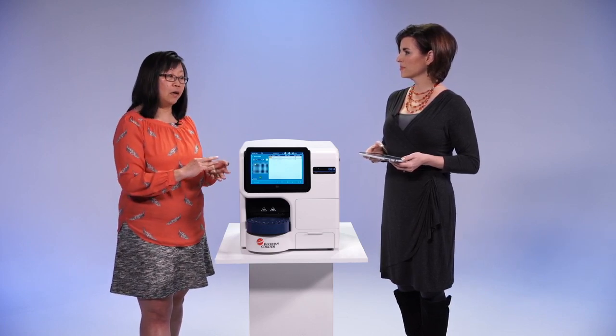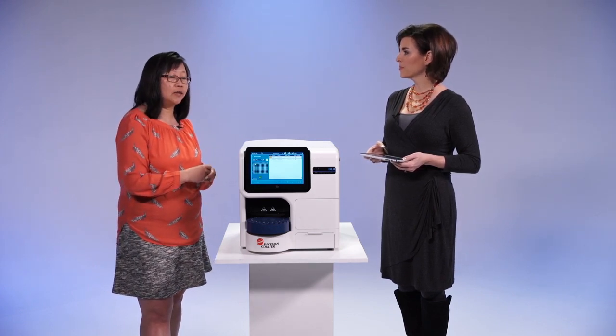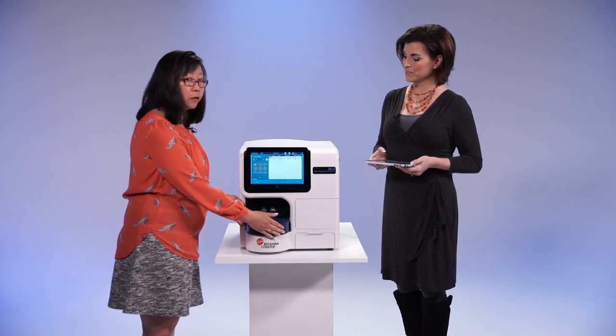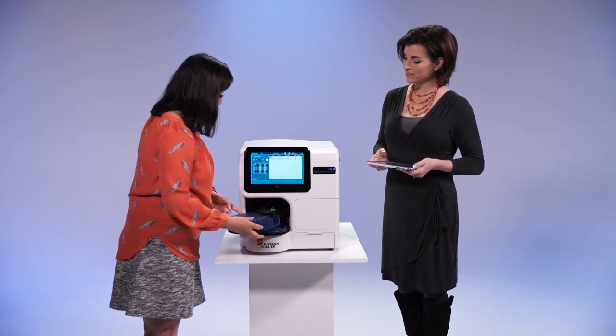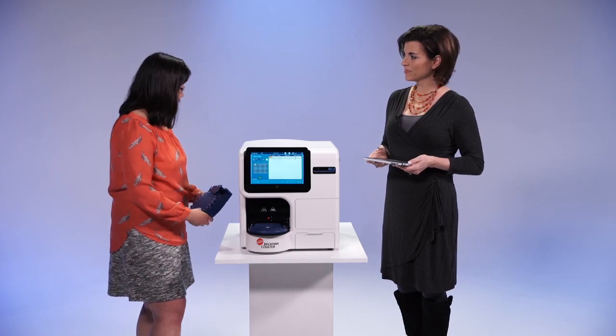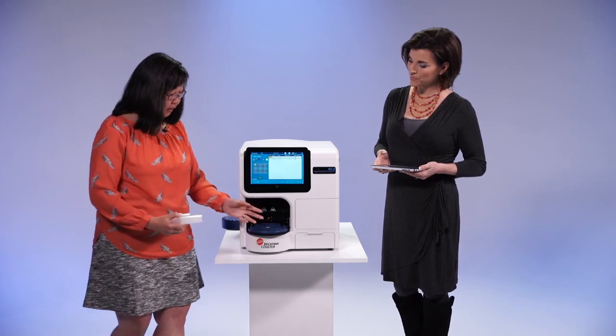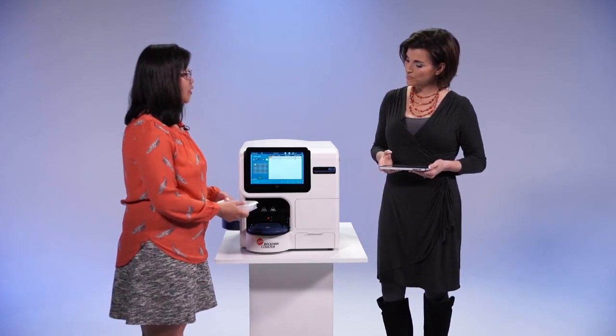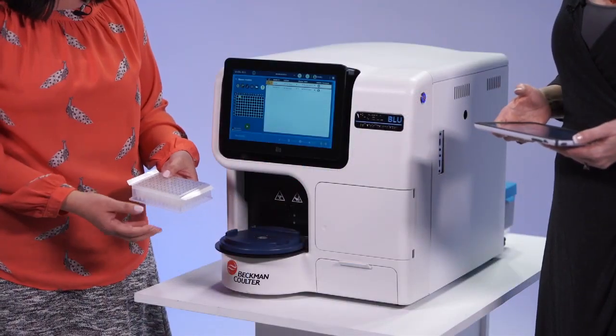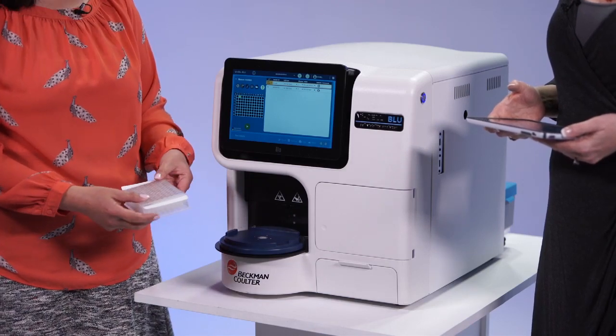There's regular mode, which is still very fast — we're able to process samples in less than 130 seconds. But in fast mode, we can go 90 seconds or less. In fast mode, we require that an exact sample volume gets added to the sample tube or plate. In that sense, we are skipping a couple of aspirate-mix steps that would normally be there in regular mode, and we also eliminate one of the cleaning steps, which helps save time. Instead of 130 seconds, we're able to go down as fast as 90 seconds. We've also added the ability to run a 96-well plate. The plate loading position is just underneath the carousel, and I have a film cover on this plate to help prevent evaporation of the samples.